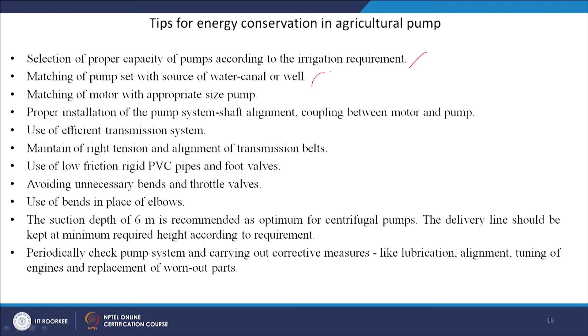Now, there are some tips for energy conservation in agricultural pumps. Select the proper capacity of pumps according to the irrigation requirement, match the pump set with the source of water, canal or well, and match the motor with an appropriately sized pump. Install the pump system properly, with shaft alignment and coupling between motor and pump, and use an efficient transmission system, maintaining the right tension and alignment of transmission belts. Use low friction rigid PVC pipes and foot valves, avoid unnecessary bends and throttle valves, and use bends in place of elbows.